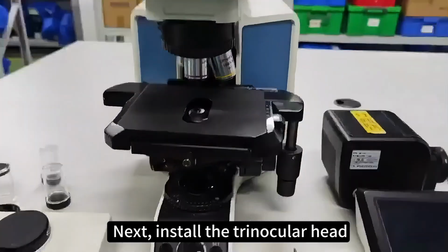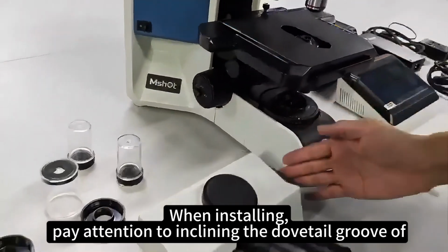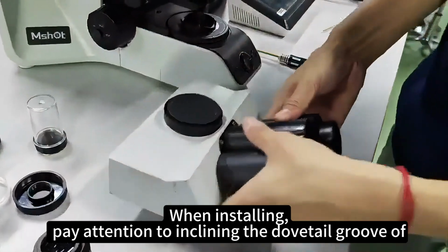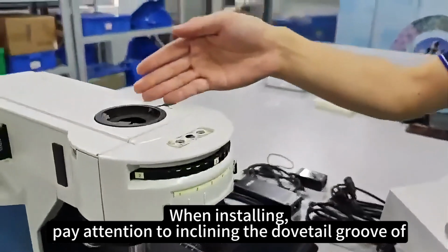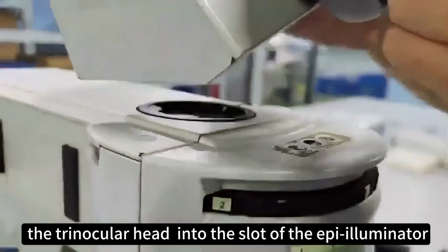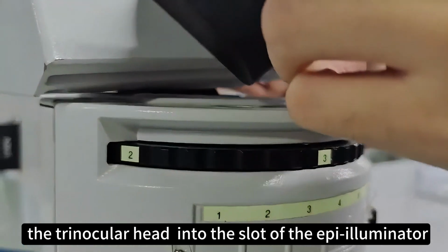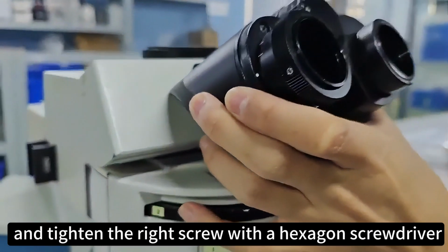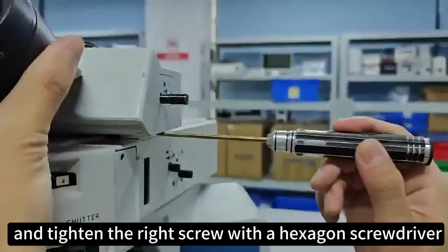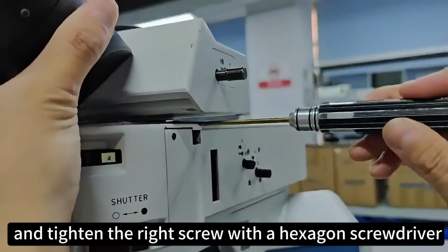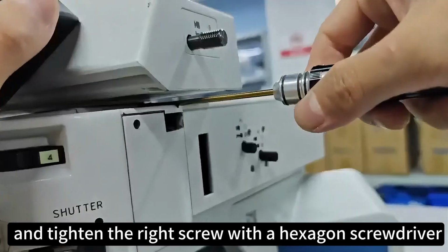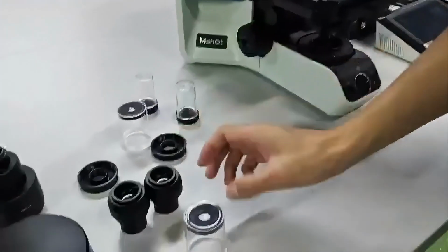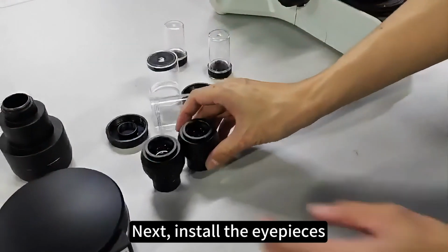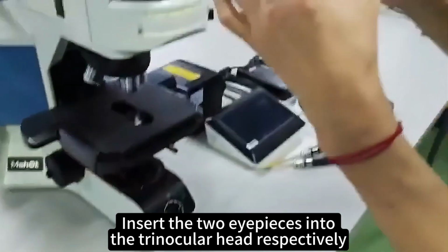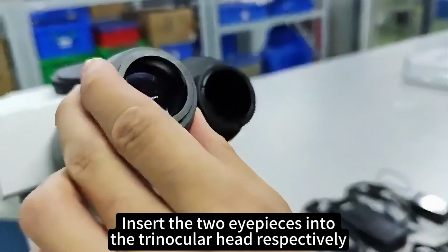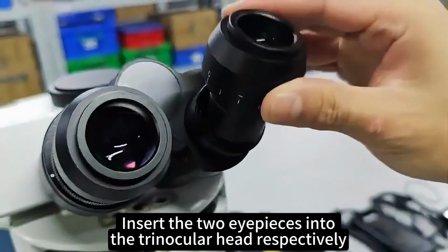Next, install the trinocular head. When installing, pay attention to inclining the dovetail groove of the trinocular head into the slot of the epi illuminator, and tighten the right screw with a hexagon screwdriver. Next, install the eyepieces. Insert the 2 eyepieces into the trinocular head respectively.